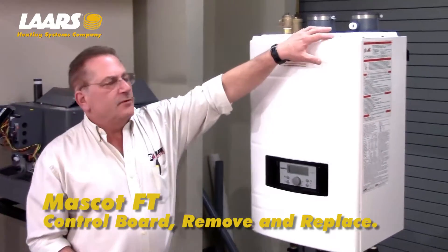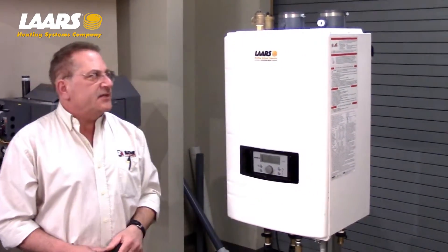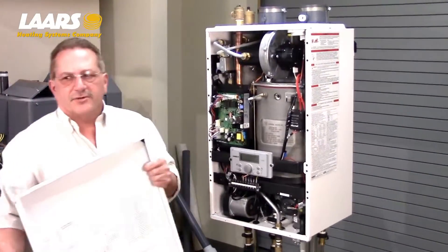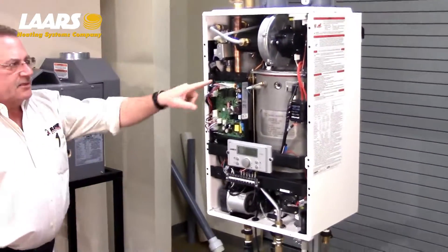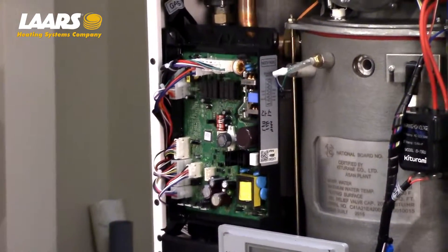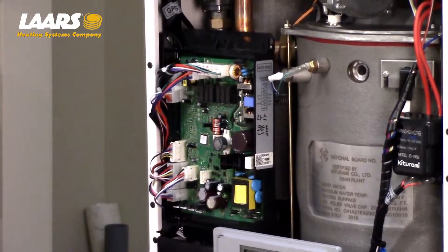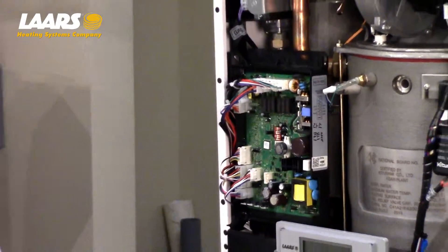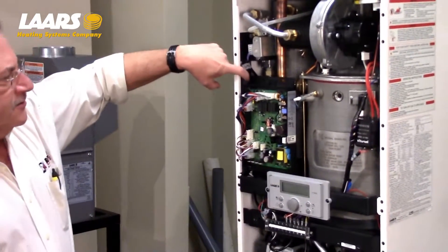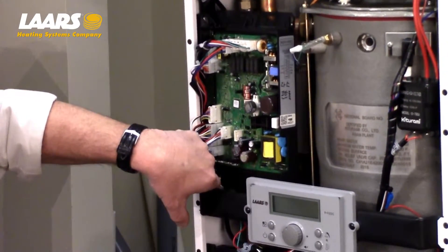As you can see, I've already removed the four screws from the cover of the Laars Mascot FT boiler. Remove those four screws with the number two Phillips head screwdriver. Here is the printed logic board. There are a series of connectors on the logic board. All of those connectors are keyed to a specific way so that you cannot make a mistake by plugging in a connector in the wrong place. There are two number two Phillips head screws that hold the printed circuit board in place.